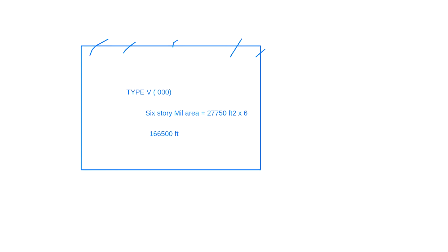In this case, we calculated the total floor area, 166,500 square feet, right? And we have to reduce 75%. Then we will come to a value of around 2,000 GPM.